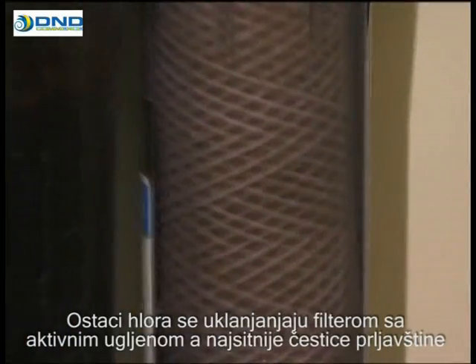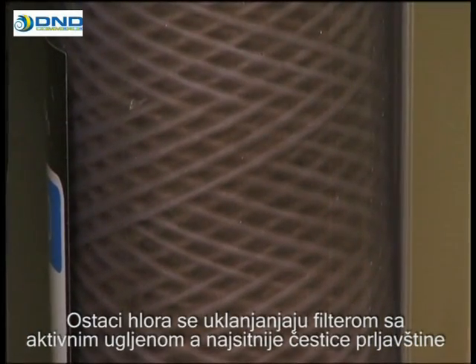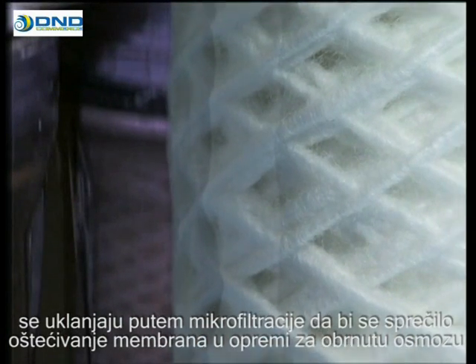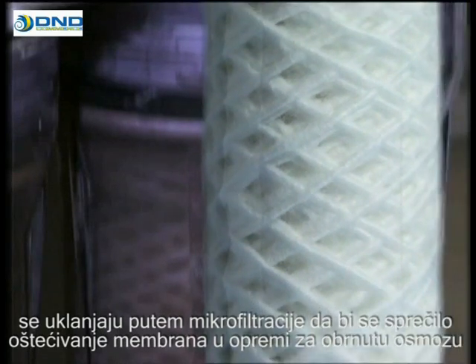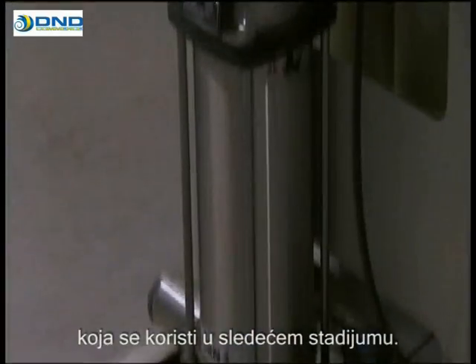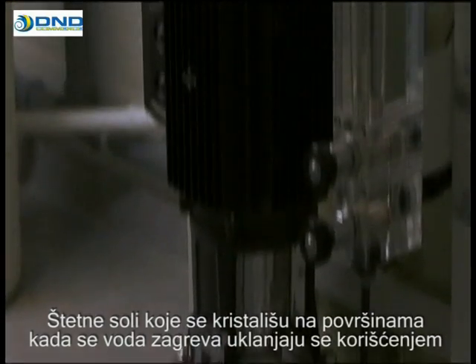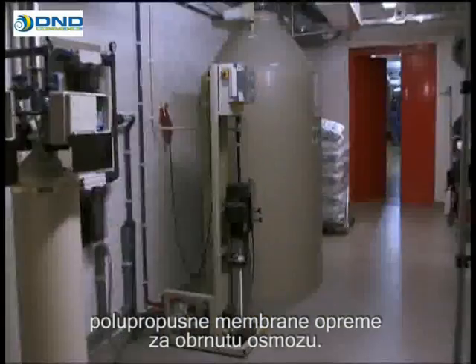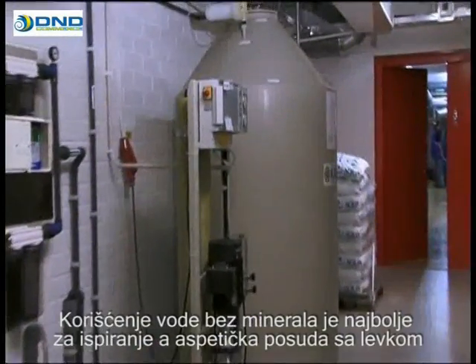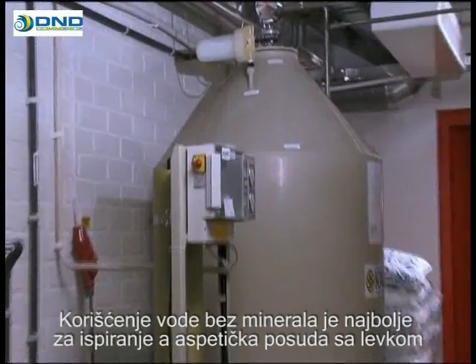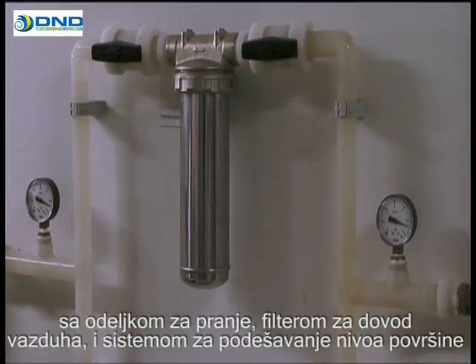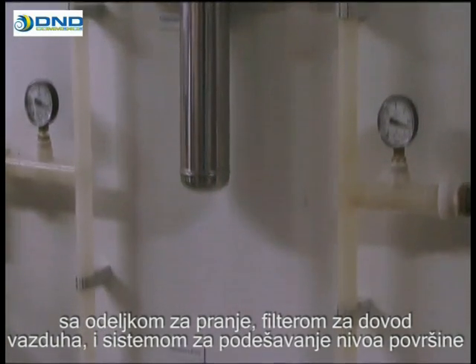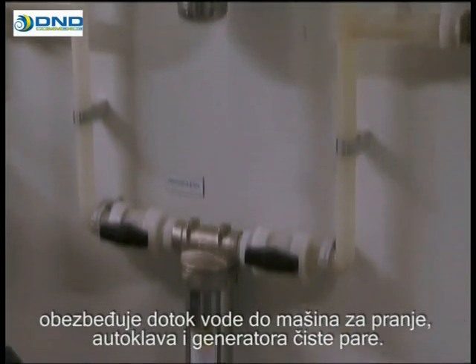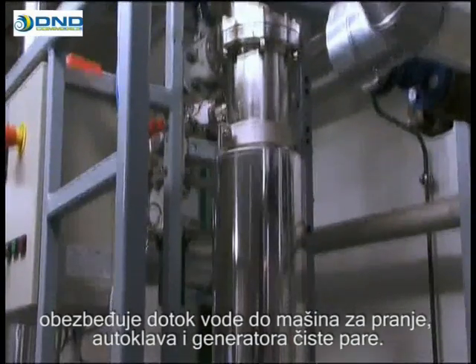Chlorine residue is removed with an activated carbon filter, and the finest dirt particles are eliminated via microfiltration in order to prevent damaging membranes in the reverse osmosis equipment used in the next stage. Harmful salts that crystallize on surfaces when water is heated are removed using the semi-permeable membrane of the reverse osmosis equipment. Using mineral-free water is best for rinsing. An aseptic funneled vessel with a washing ball, air supply filter, and a surface level adjustment system supplies water to the washers, autoclaves, and the pure steam generator.